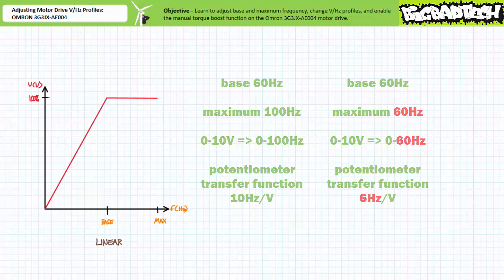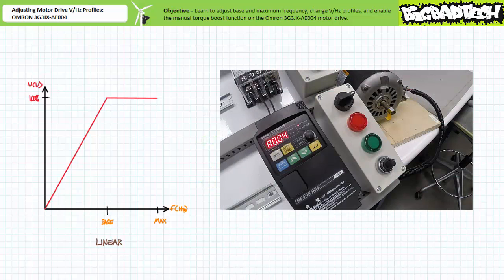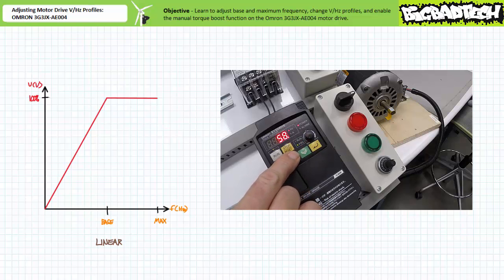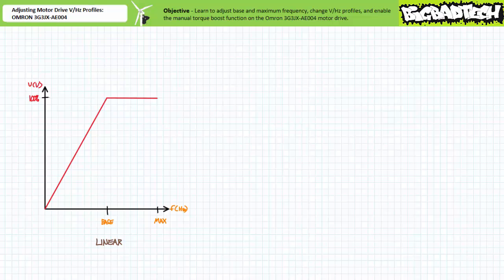Let's see if this is the truth. Navigate to parameter A004 maximum frequency. Select mode, decrement from the previously saved 100 hertz back to 60 hertz, then select enter to save it. This motor drive has now been programmed to scale the zero to 10 volt analog voltage input of the external speed potentiometer from zero to 60 hertz in 6 hertz per volt divisions.